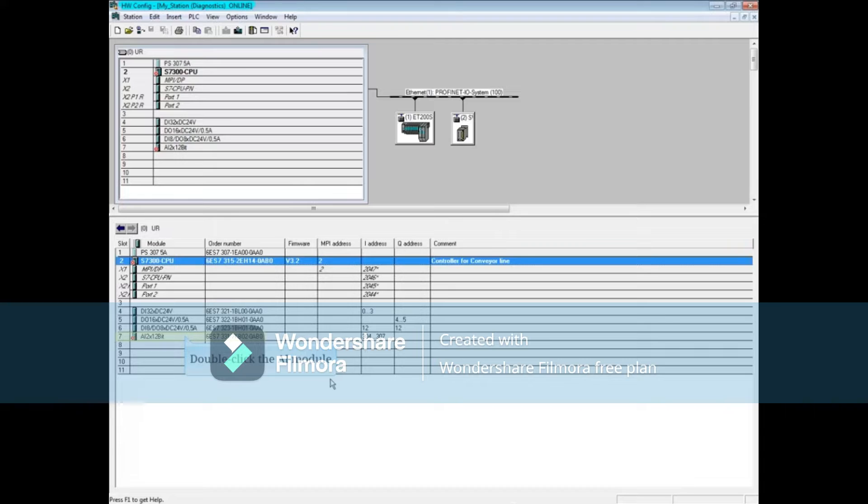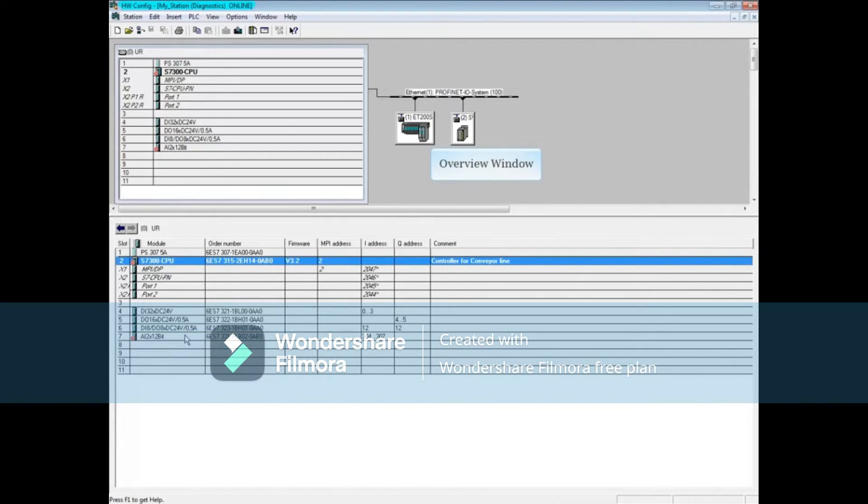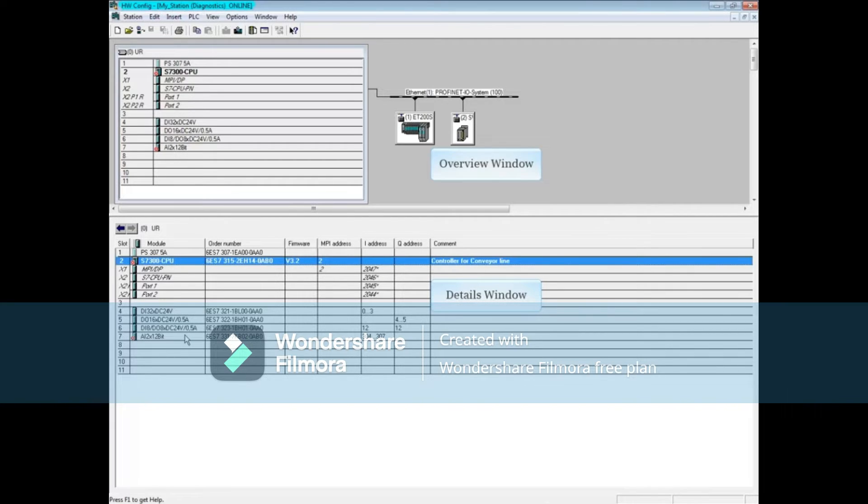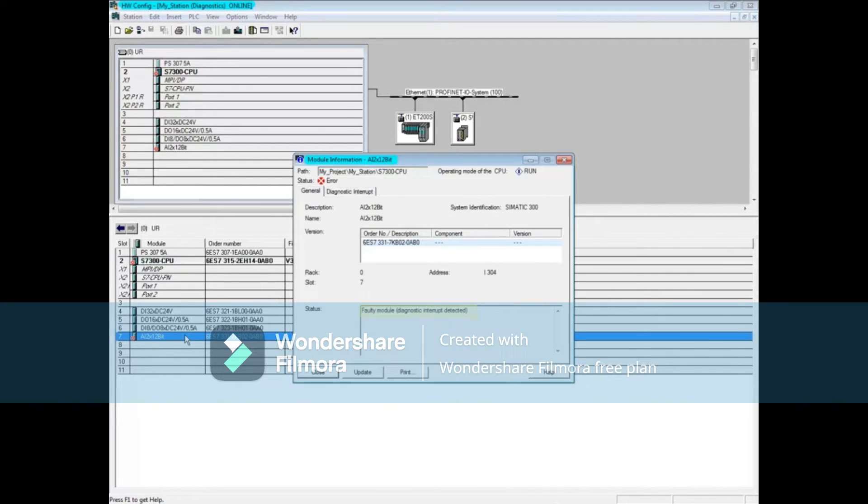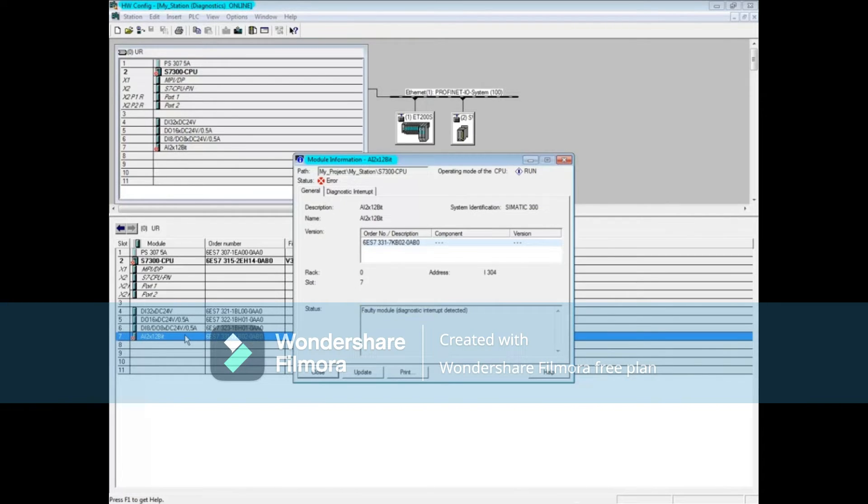Double-click on the analog input module. You can do this either from the overview window or the details window. The general tab shows that a diagnostic interrupt has been detected. Click on the diagnostic interrupt tab.